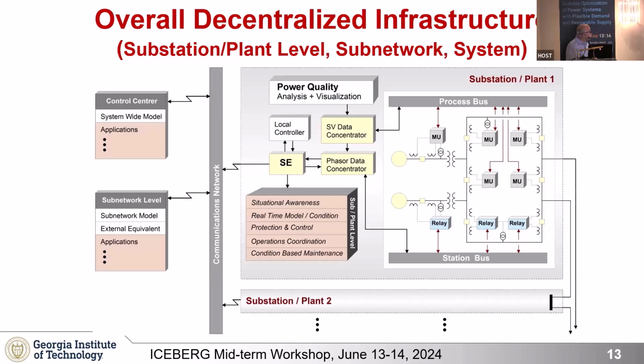Typically, we collect the data from the relays into the station bus, and the data from the merging units into the process bus. The difference in terminology is that in the process bus we have sample data — points on the waveform of voltages, currents, temperatures, rotational speed of generators, and so on.